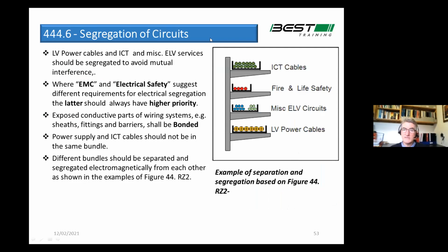Okay, a little bit more, it talks about segregation of circuits. What you see in the diagrams is a similar diagram in the wiring rules. It's just common good practice that we all follow as designers or contractors. We segregate our LV circuits from our ELV. So that's mandatory because ELV circuits is usually safety extra low voltage, and it's a requirement in part 41 to segregate the 2 types of services anyway. And then when you read the various standards, IS3217 and IS3218, it talks about segregating fire alarm and central battery emergency lighting circuits from other circuits. And that applies to all life safety circuits, basically.